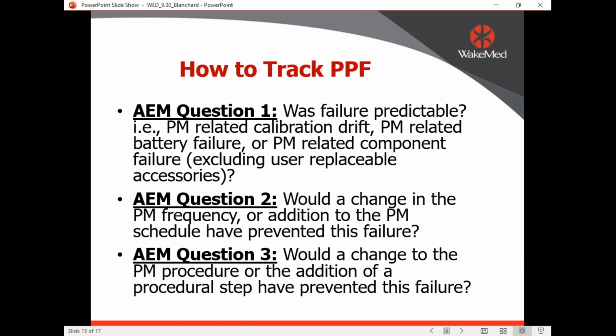And we ran those. So when I say 2 years, that's our bare minimum. I think we had it on for 5 years for those because we had so many and we wanted to make sure we got this one right. Anything under 2 years, we don't even look at. Once it hits that 2-year window, then we can start looking at whether the data shows something should be brought on. But for infusion pumps, we change the battery out every 5 years. That's the only maintenance that we do.